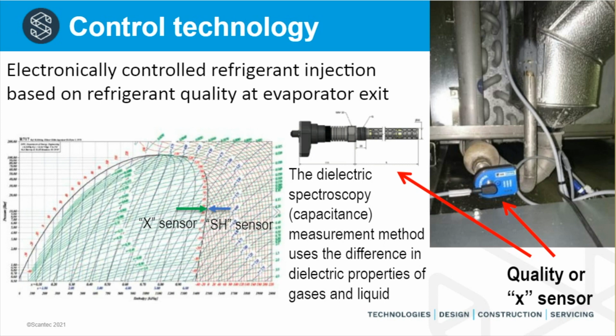Let's not get into too much detail about how this sensor works. This is frankly a matter for the manufacturer. These things come from Denmark from a company called HB Products. What you see there on the shot on the right is one way of installing the sensor. There are other ways. In some of the later plants, we have removed the sensor from the refrigerated space and up into the ceiling space, where it's much easier to service, and it doesn't jeopardize the ability to control the refrigerant injection into the evaporator.